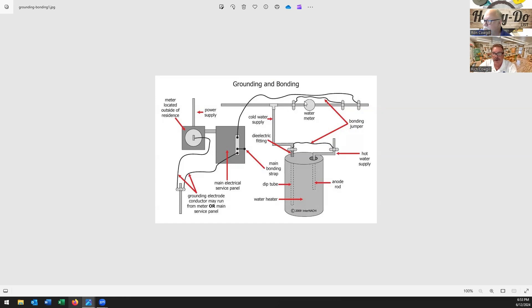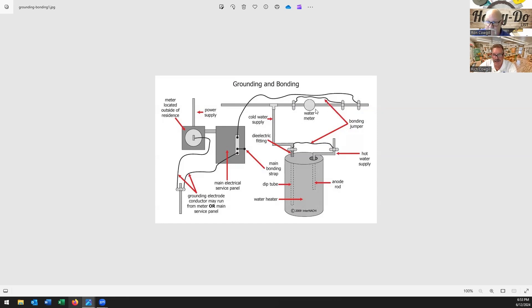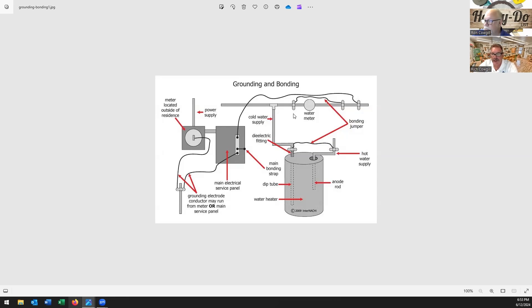And probably more importantly, when you see that water line on the top there and where the water meter is, you see they put a jumper across. Because if you pull that water meter out, guess what happens? Yeah, you no longer have - you're breaking your bonds. So you have to put the jumper over the meter. Same thing with your water heater - just because the two lines go in there doesn't mean they're going to have the same potential, so you jumper across over the water heater.